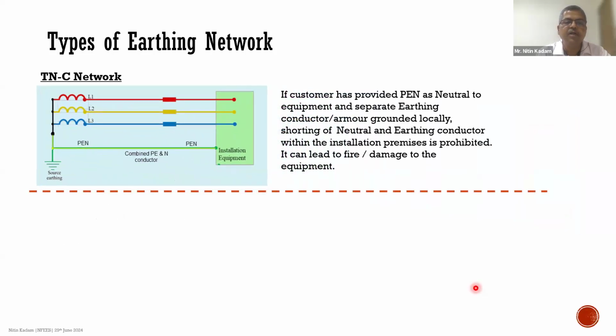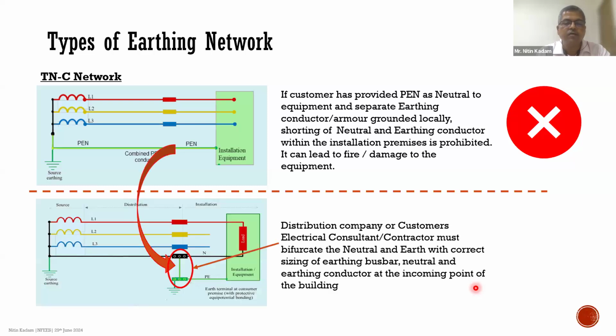Somehow there is a misconception, and people try to connect the common PEN conductor, the neutral, and the armor if it is grounded locally, and they try to short this within the installation. After the main panel or the meter room, they try to short this in the building premises, and this is not recommended, because when you do this within the installation, it can lead to fire or damage the equipment. So what should be done? You should ask the distribution company or the customer's electrical consultant or the contractor to bifurcate the neutral and earth with the right sizing of the earthing busbar, neutral, and earthing conductor at the incoming of the building, and then it is distributed as separate neutral and earth. This is the right approach, and this should be done.